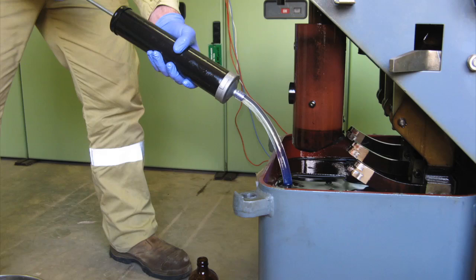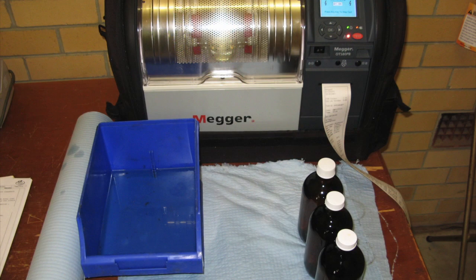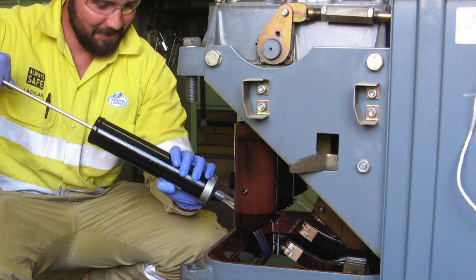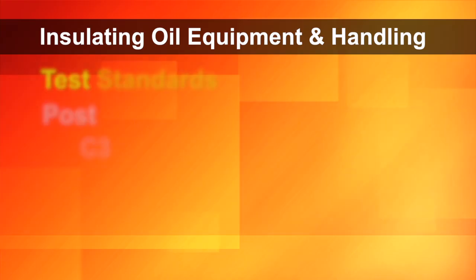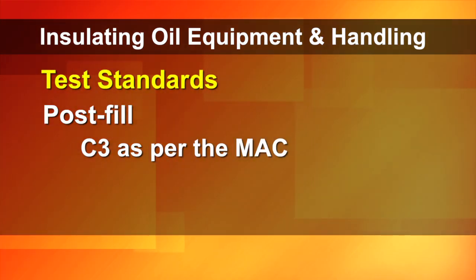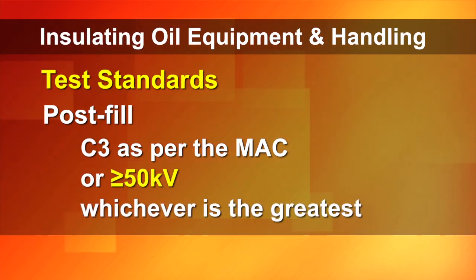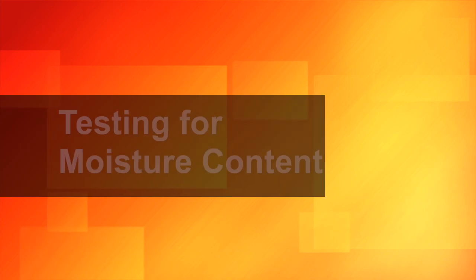One more thing we have introduced under this process to remember is that when you have done a complete refill on a circuit breaker or piece of plant, we require you to do a post-fill sample on that. That's to make sure that when you filled up that piece of plant that it didn't have moisture in it or contaminants in it. The criteria for a post-fill test are C3 as per the maintenance acceptance criteria, commonly known as the MAC, or 50 kV, whichever is the greatest of these two.